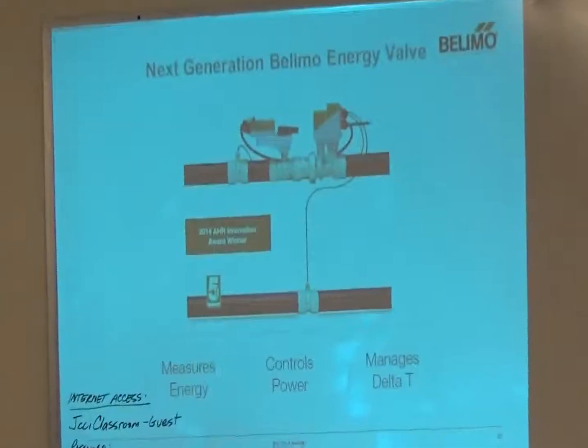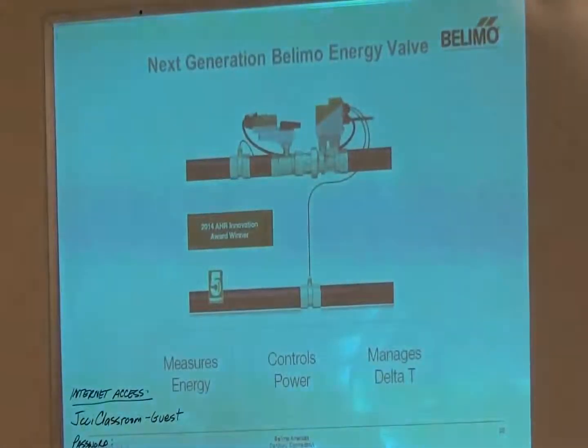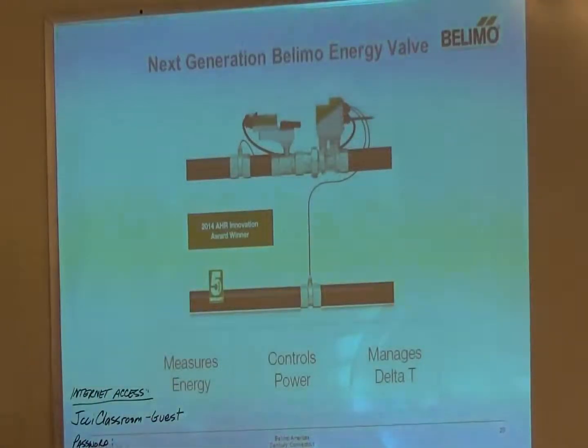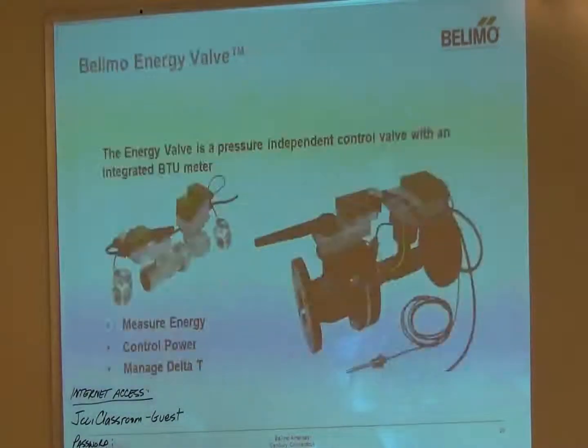So what is the energy valve? Why is it different from a standard pressure-independent valve, from a pressure-dependent valve? Well, like I said, it is a pressure-independent valve. It is one where we can measure energy, control power, and manage the delta T. So you can see here, this is the large version. I see why I don't carry that around with me. Before we brought the small one out, that was all I had, so I did lug that around.